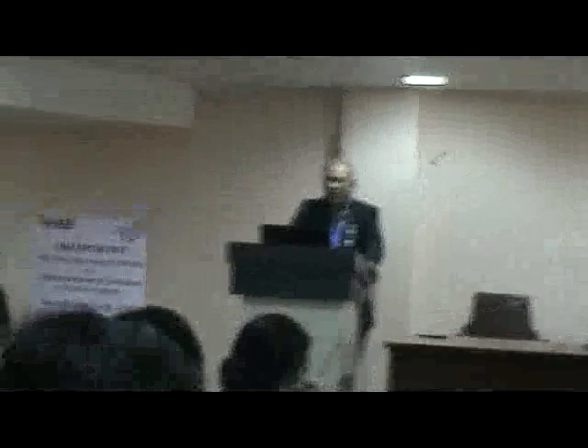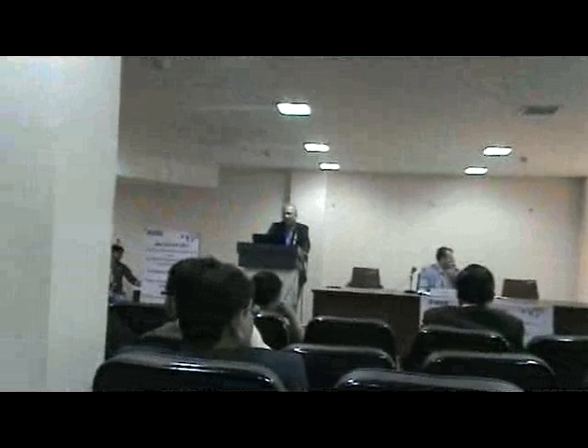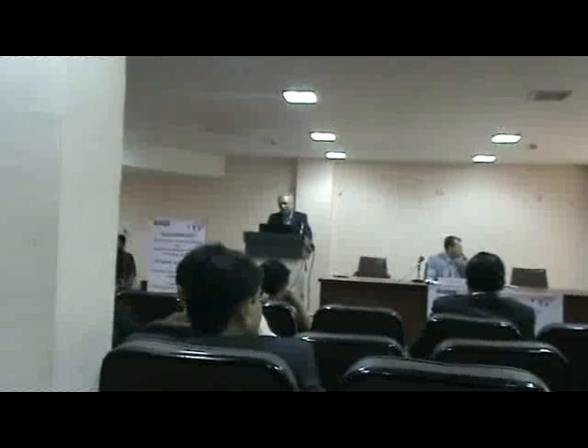Another system finding increasing acceptance is the MV bundle system with a semiconductor outer layer with no metallic screen and a bare messenger wire. The touch-safe property of the bundle is achieved by connecting the bare messenger to the earth. This system has been found attractive in Ireland based on feedback of Australian experience.